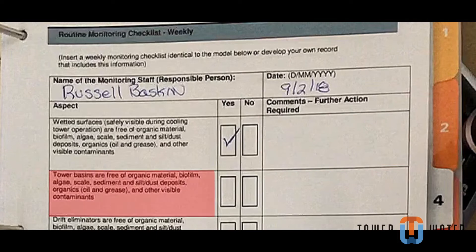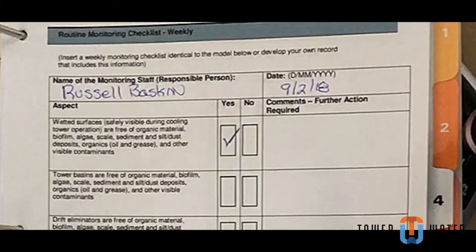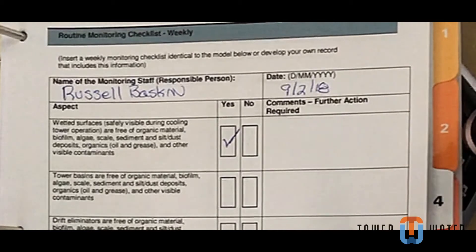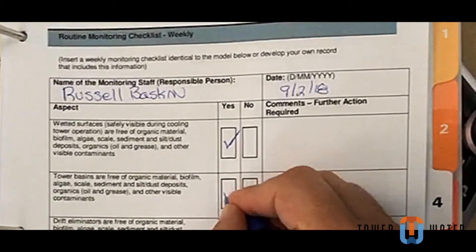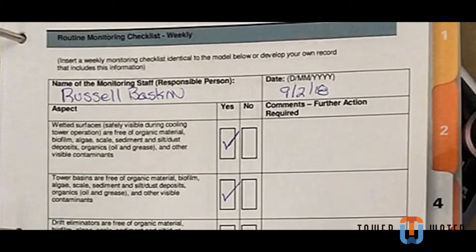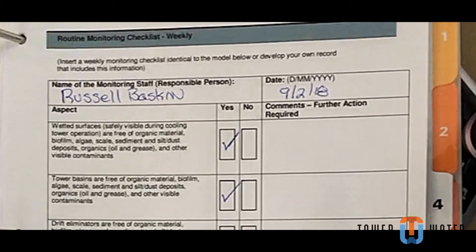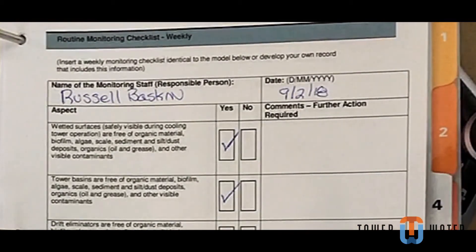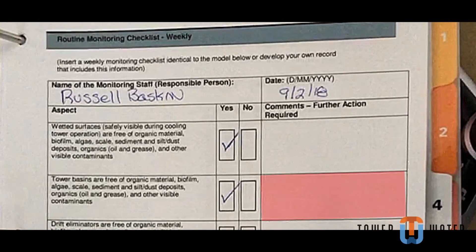Question 2: Tower basins are free of organic material, biofilm, algae, scale, sediments, silt, dust deposits, organics such as oils and greases, and other visible contamination. Check yes if basins are clean or mostly clean. Check no if basins contain contamination. If you check no, in comments write where it exists, when and how it will be removed.